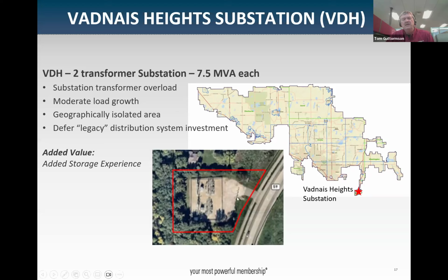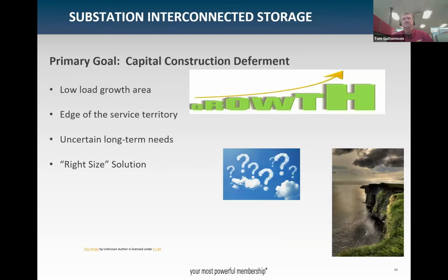We thought that would be a good opportunity to put in a battery at the substation, charged and ready to go during peak times, so it could supplement energy to feed the grid during backfeed outage scenarios, without being overkill. This substation really fit that criteria, so we did a study and went out for bid to see if it would be cost-effective. It's a low growth area at the edge of the territory with long-term needs but probably not a lot of growth, so it seemed like a good right-sized solution.